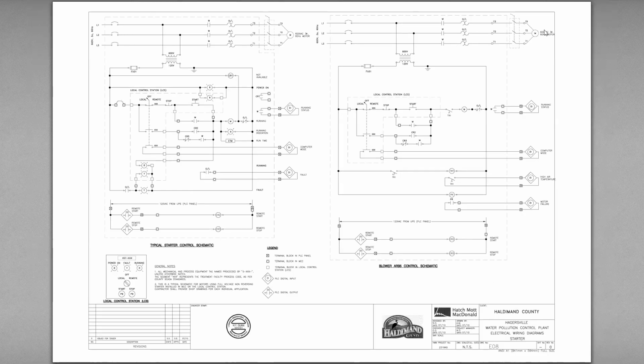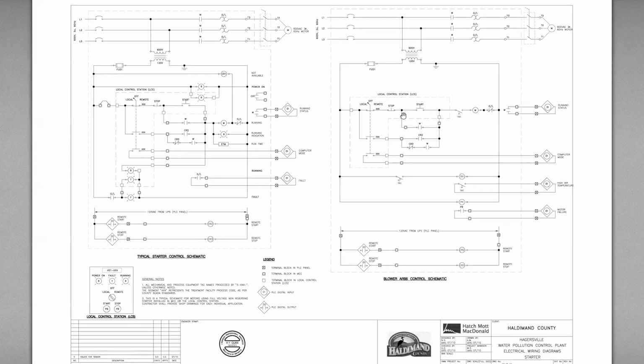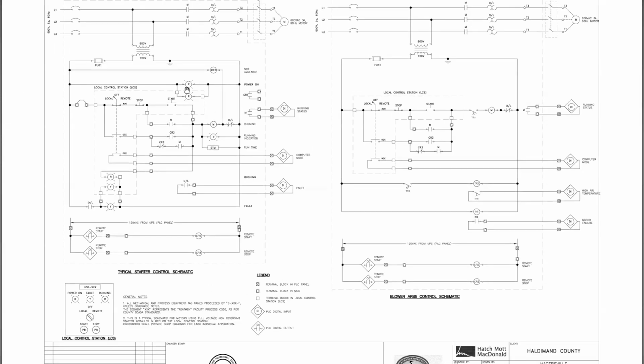These are examples of 600-volt motor circuits without VFDs. So we've got 600 volts run across to the motors. We've got 600 volt to 120 volt step down transformers. We've got local control stations for those pumps. We can see here, we've got the same 120 coming into a CR1, which is not available. So it looks like they're going to use somewhere in the drawing a not available, normally closed contact.